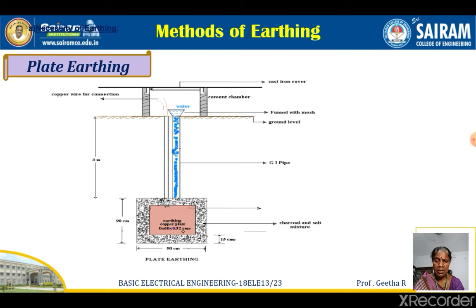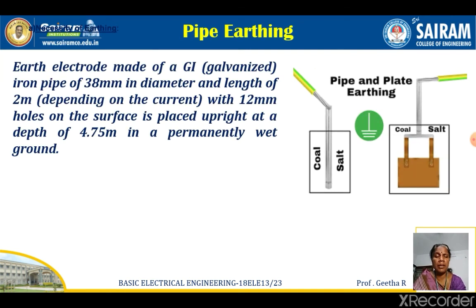Here the copper plate is placed vertically. At the side it is filled with charcoal and salt. Here one GI pipe is given with a funnel through which water will be poured to maintain the electrode resistance well below the required value. Here the earthing wire is connected to the plate. It is called plate earthing. Next one is pipe earthing. In plate earthing a plate is used; in pipe earthing, just a pipe is used, and the wire is fixed to the earth or ground.